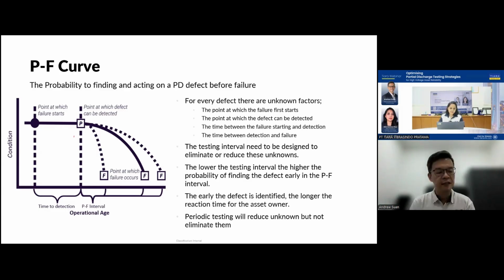So if it's a surface discharge, we always tell our customers, once surface discharge is detected and we confirm it's a real PD signal, please take action ASAP, because for surface discharge the time to failure is very, very short compared to internal discharge. For internal discharge, sometimes the point to failure interval can be quite substantial, meaning months or even years before failure happens.